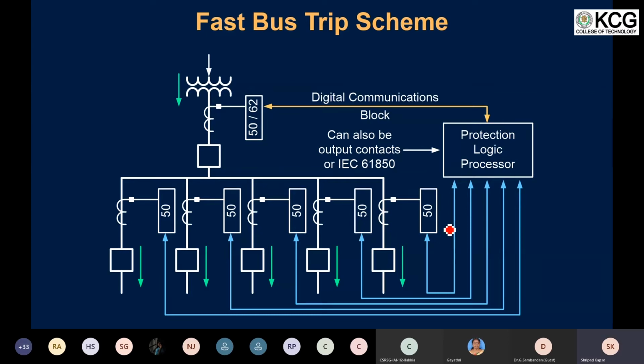So these kinds of communication protocols require communication between the relays to occur, and there is a possibility of cyber issues or cyber security related concerns when we connect all these relays on a communication protocol, or on an Ethernet switch, and we are communicating things to the incomer breaker. So there is also a risk, not only related to the delay in the operation of this kind of system, there is also a risk associated with cyber threats.